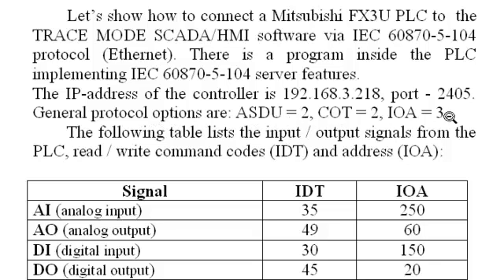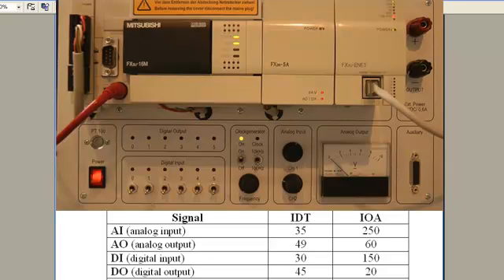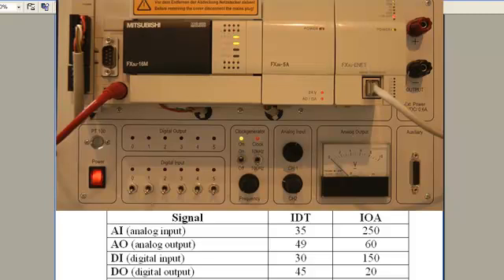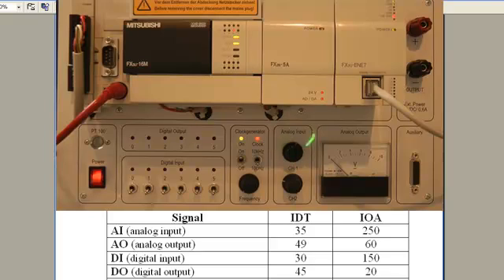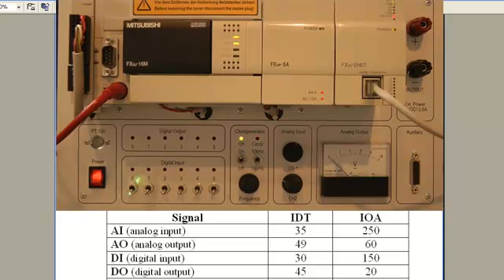General protocol options are ASDU=2, COT=2, IOA=3. The following table lists the input/output signals from the PLC, read/write command codes (IDT) and addresses (IOA): analog input, analog output, digital input, and digital output.